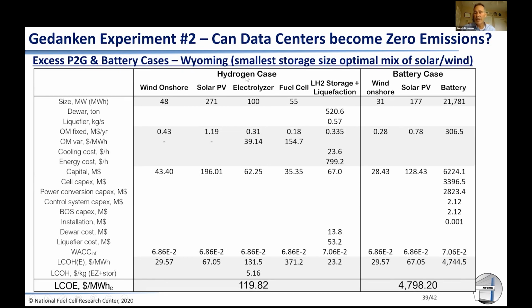We're accounting for that. We have to buy an electrolyzer, we have to buy a fuel cell, but the electrolyzer can be independently sized from the fuel cell. Notice the megawatt size of the electrolyzer is 100 and the fuel cell is 55 for a 50 megawatt data center, because the fuel cell can be sized just to meet the maximum amount of power the data center would ever have at deficit.